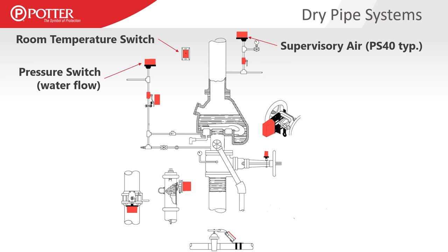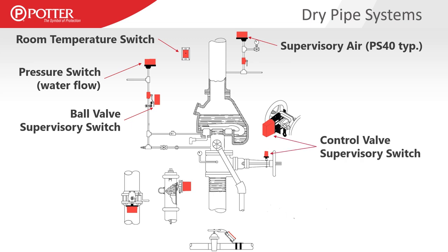Room temperature switches monitor room temperature, which is critical in a dry pipe valve enclosure. The pressure switch for water flow operates similarly, along with ball valve supervisory switches that are important again to prevent that ball valve from being inadvertently left closed — thereby eliminating the value of the pressure type flow switch on that side of the dry pipe valve. We have more control valve supervisory switches, just like on the wet pipe system, and they can be in several different configurations.